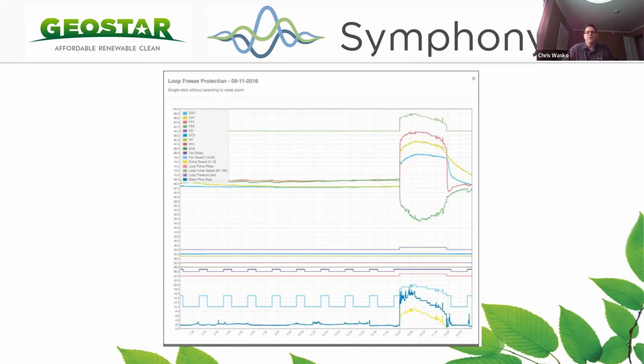If the unit sends you an email and says, hey, I'm having problems here, I'm starting to shoot out some fault codes, you can go back in and look at the exact time the fault codes were coming out, and pinpoint exactly what was going on with the whole system, including the compressor staging at the very moment it passed out that code. So you can determine maybe there was something happening electrically, or part of the system wasn't running, and pinpoint exactly what's going on before you even make the phone call to the consumer. You can call them up and say, hey, look, we've seen there's a fault going on. Maybe the homeowner lives remotely from the home you're working on, they're on vacation. Hey, you've got a problem there, here's what we need to do to fix it.